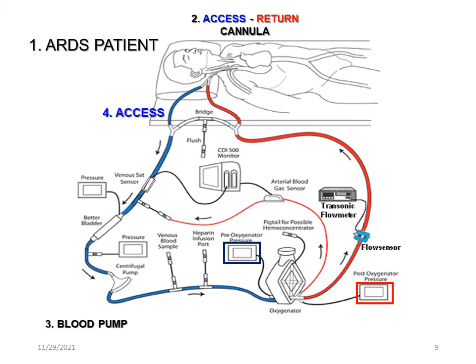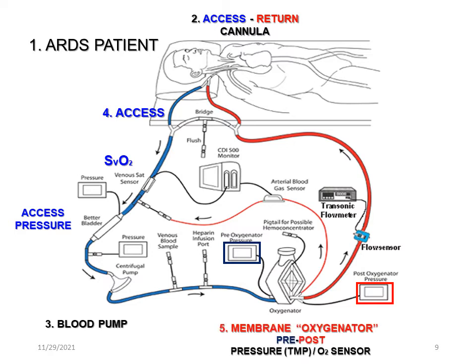Then we have the access line where the blood is being extracted from. It creates a negative access pressure, and the SVO2 in most circuits is being measured. So the saturation of the venous blood is being measured, and it will be low because it's desaturated blood. This is sometimes referred to as the pre-saturation oxygenation level. Then the blood goes to the membrane oxygenator and a pressure is measured, a pre-transmembrane pressure, TMP, and a post-transmembrane pressure. It's also connected to an oxygen sensor. If either of these become too high or too low, it will alarm, informing the healthcare provider, the nurse, the perfusionist, the physician, if there's an issue.